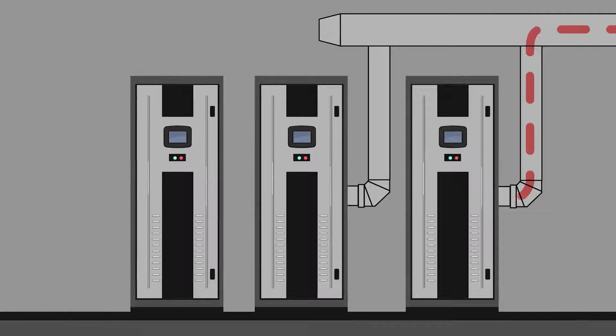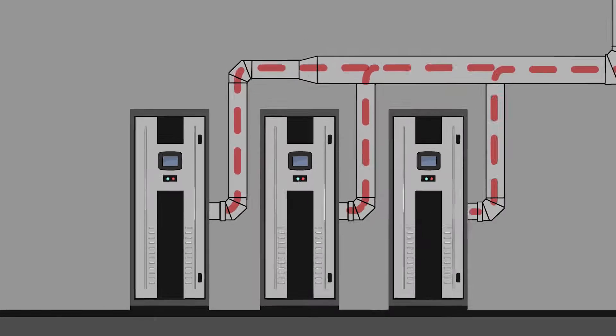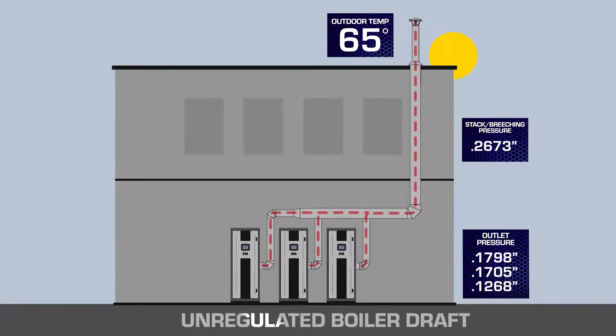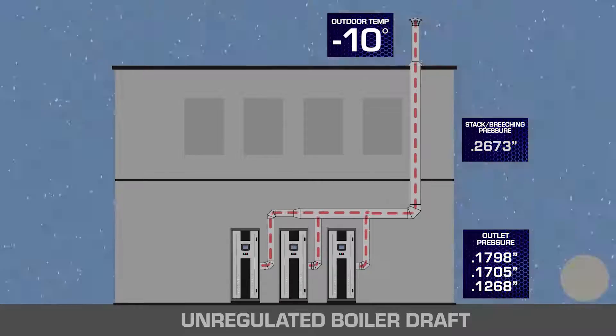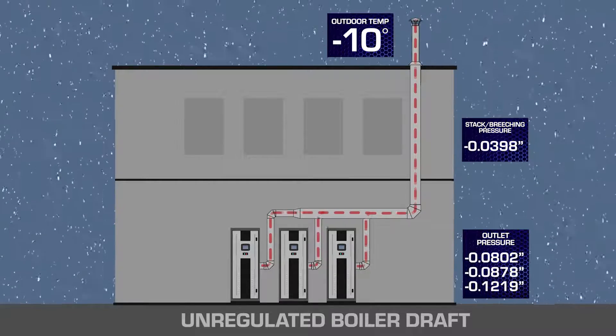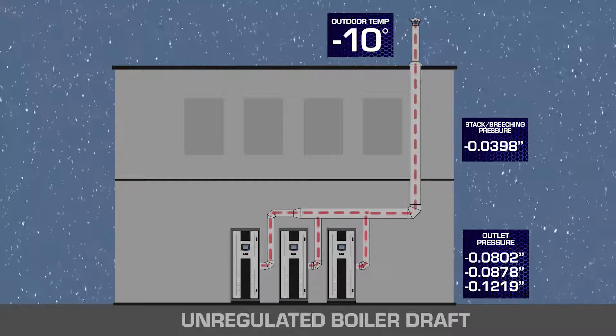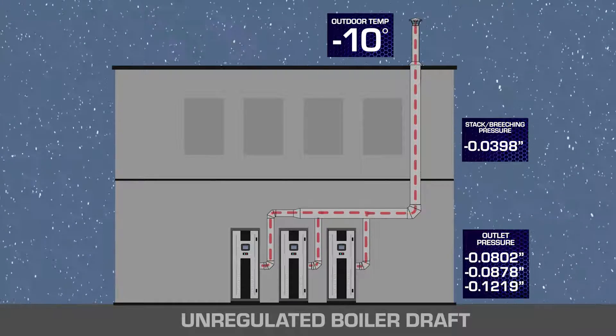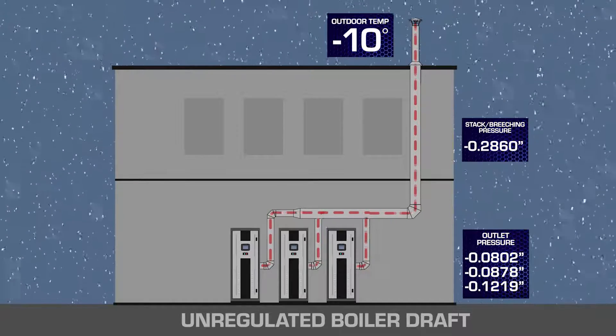When we try to common vent high efficiency appliances, the sizing needs to be done to ensure that all appliances can operate under high ambient temperature, poor draft conditions, and at full firing rate to make sure the stack is large enough to get full BTU use out of all appliances tied into a common. To ensure there's no back draft through unfired appliances, note the negative outlet pressures of the appliances tied into a common — which means again we're at Category 2 operation, a loss of efficiency, and a risk of flame instability.